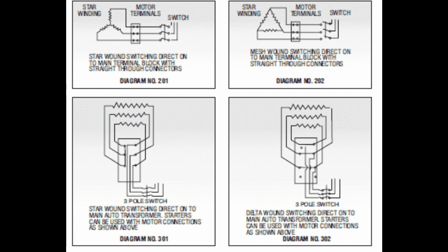Star delta starter cannot be used here. In 202, standard delta connection will be made within the motor itself, so again you cannot change it. You cannot use star delta starter. If you want to start the motor in 201 and 202, you can use either direct online method or auto-transformer starter or VFD.